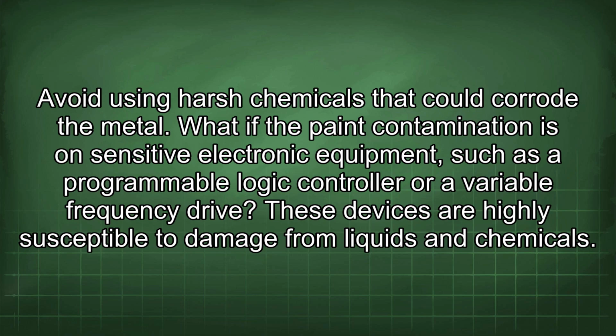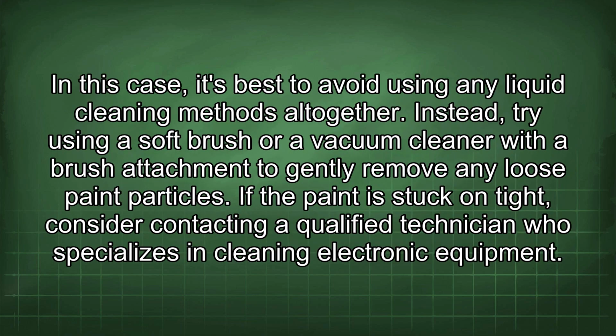What if the paint contamination is on sensitive electronic equipment, such as a programmable logic controller or a variable frequency drive? These devices are highly susceptible to damage from liquids and chemicals. In this case, it's best to avoid using any liquid cleaning methods altogether. Instead, try using a soft brush or a vacuum cleaner with a brush attachment to gently remove any loose paint particles.